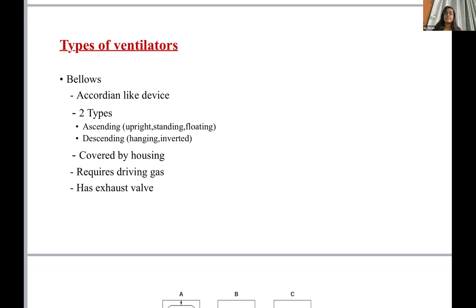So there is a driving gas flow in the bellows assembly, which enters into the bellows assembly and increases the pressure within the assembly. Because of this increased pressure, there is compression of the bellows, which pushes the respiratory gas into the breathing system and it's delivered to the patient. At the end of the inspiration, the exhaust valve is open, from which the driving gas is pushed out, which in turn reduces the pressure inside the chamber, and the bellows unit goes back to its original shape. Apart from the exhaust valve, there are also two other valves present in the bellows system, that is the safety relief valve and the spill valve.